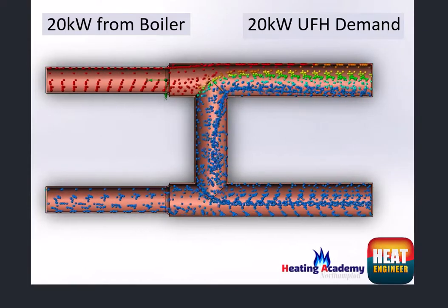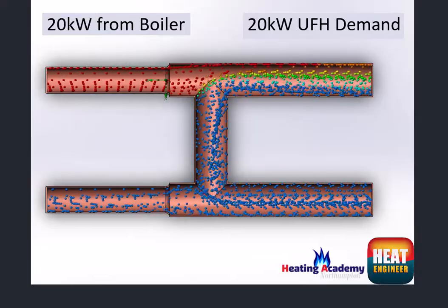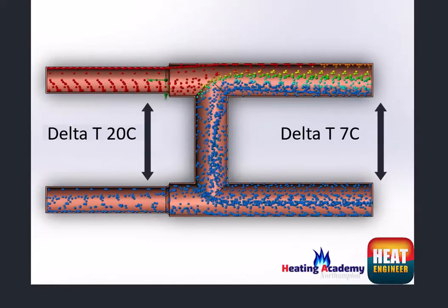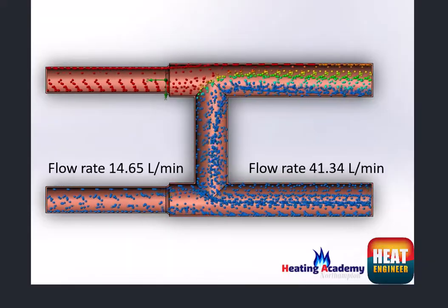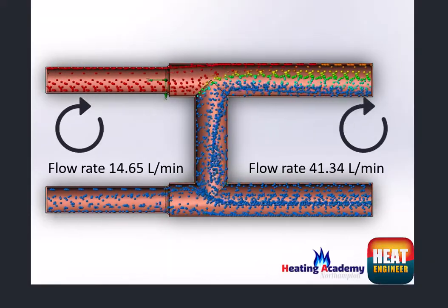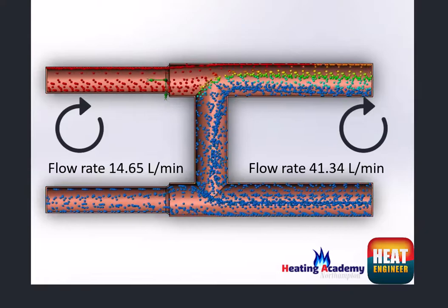So we've got 20 kilowatts coming from the boiler and we need a demand equal to that for the underfloor heating system, but the delta T requirement is different, which would mean the flow rates are different for each particular circuit, but we do have hydraulic separation here.